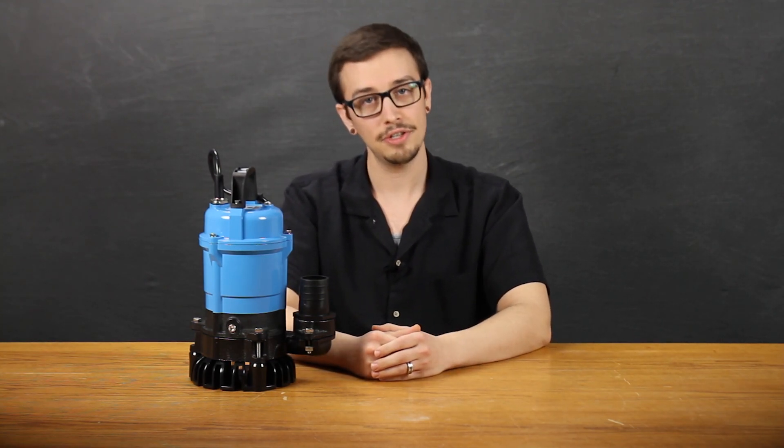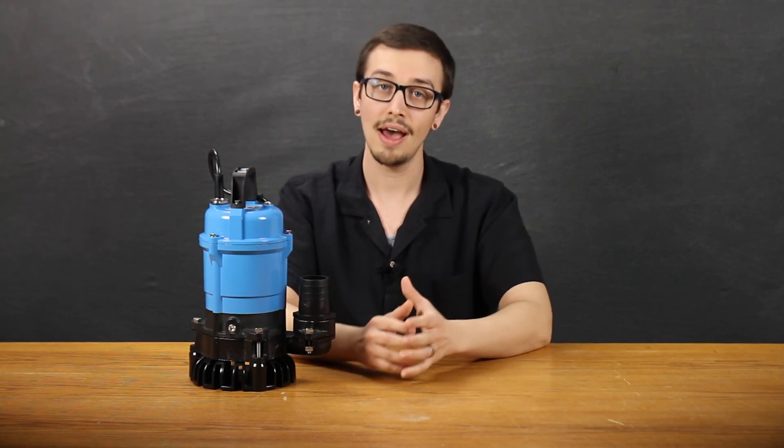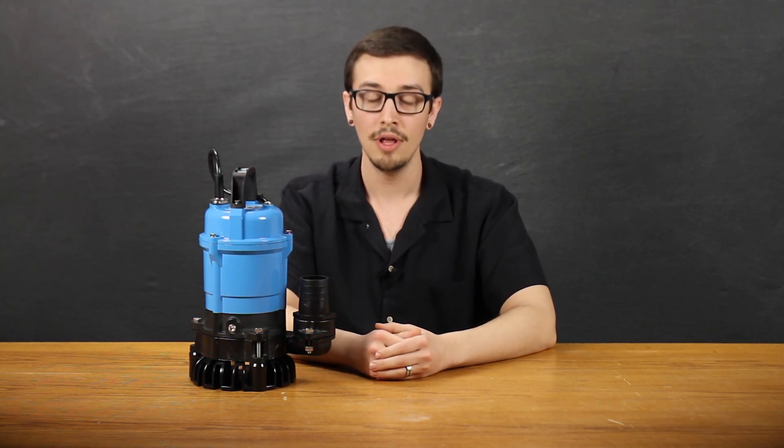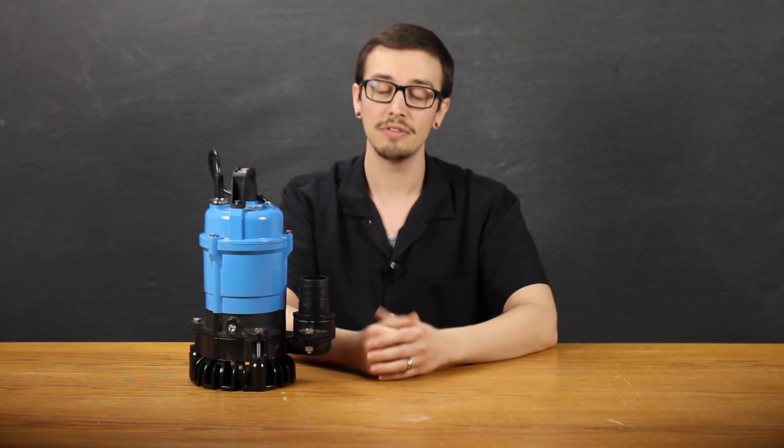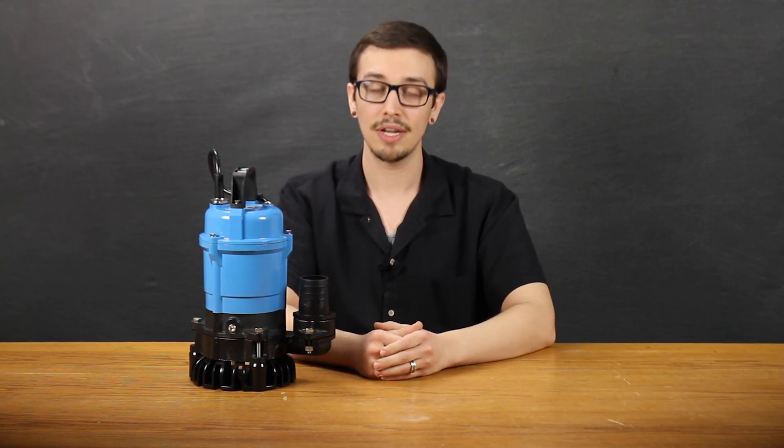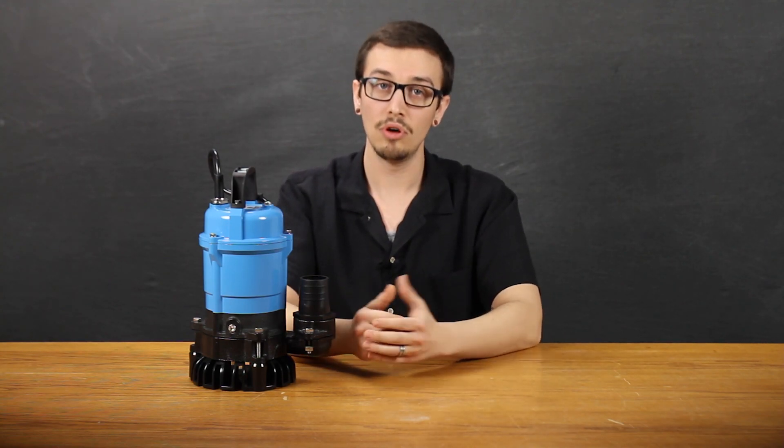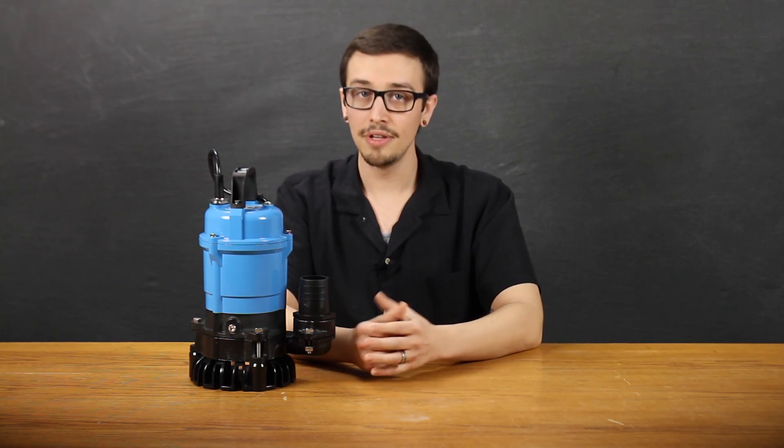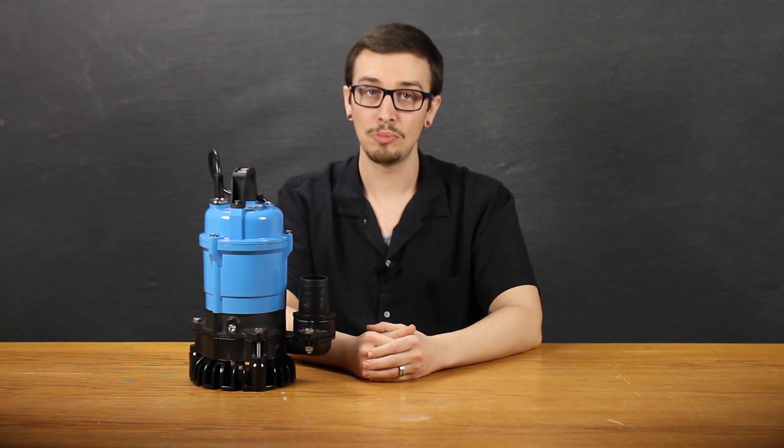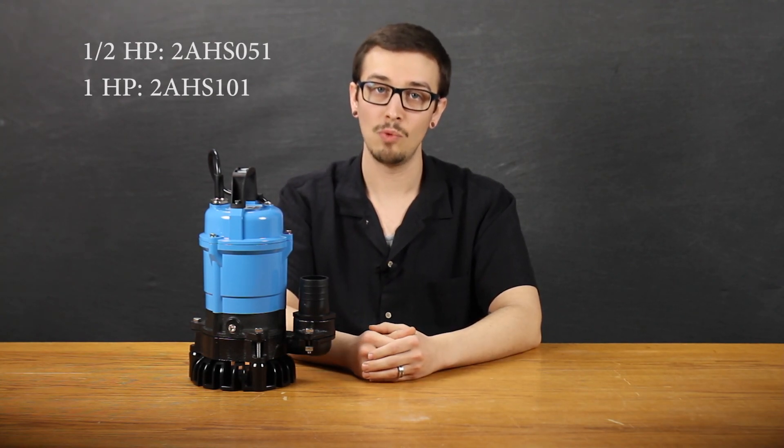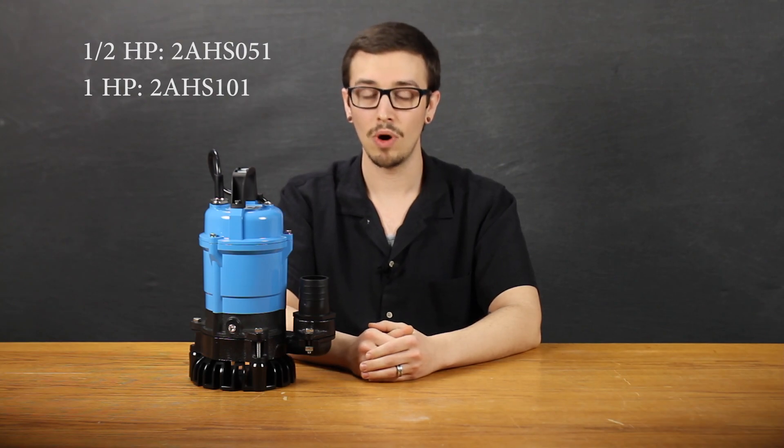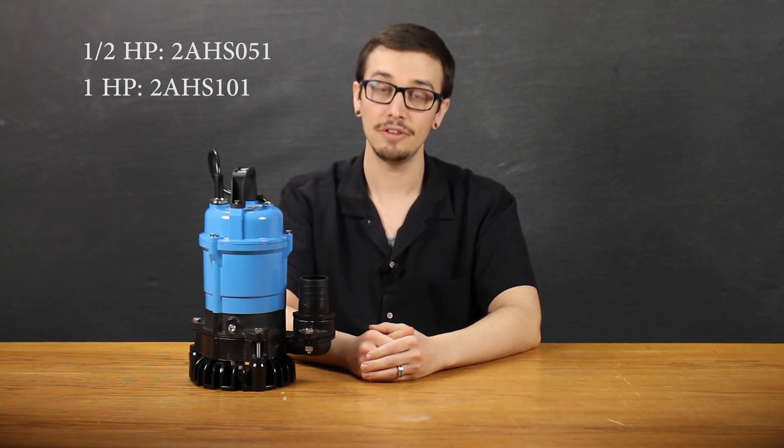The Bar Mesa 2AHS series boasts either a one-half or one-horsepower motor, but is only offered in a standard 120 volt single phase configuration, and is rated at 6 or 12 full load amps, respectively. The model number for the half or one-horsepower configuration is signified by either a 051 or 101 after the 2AHS.